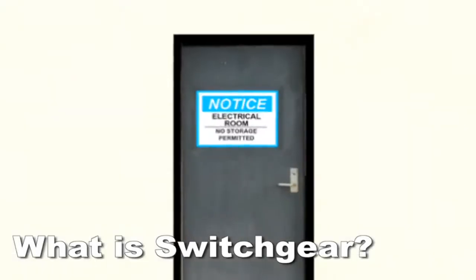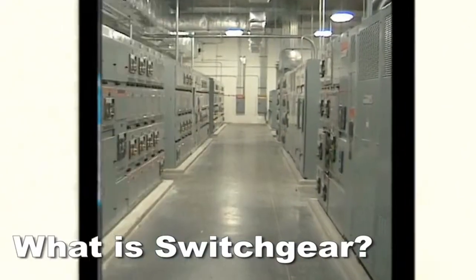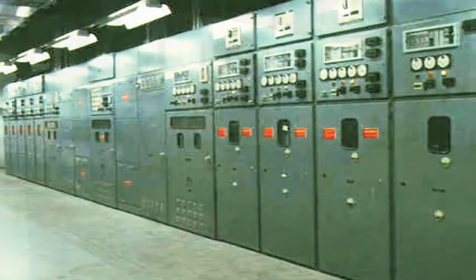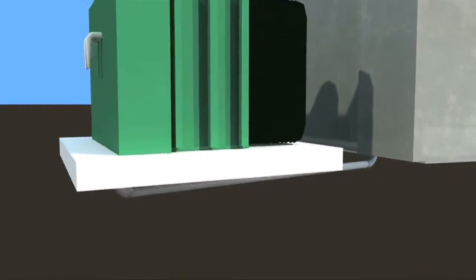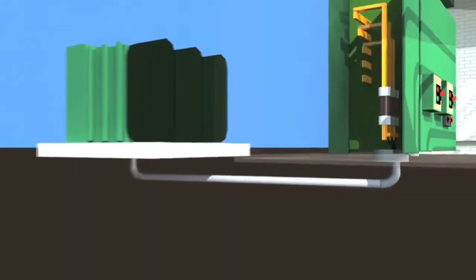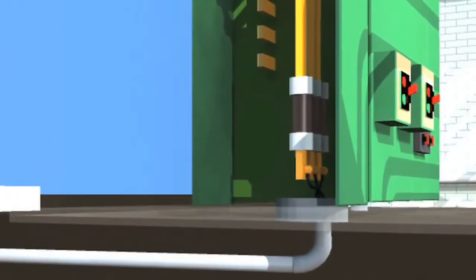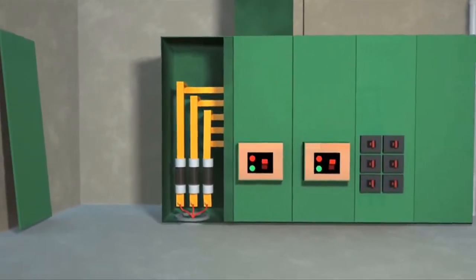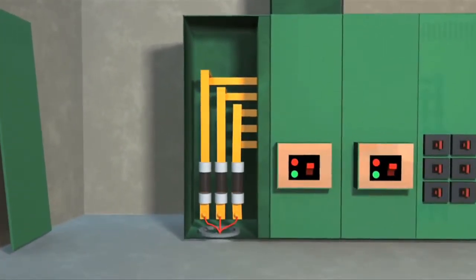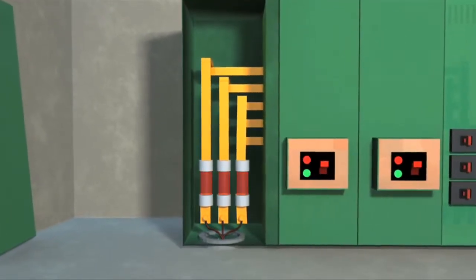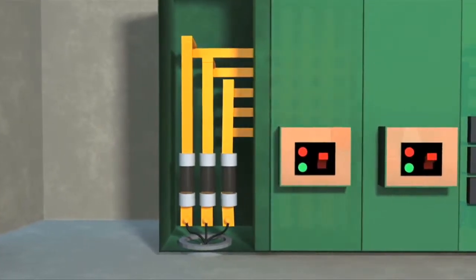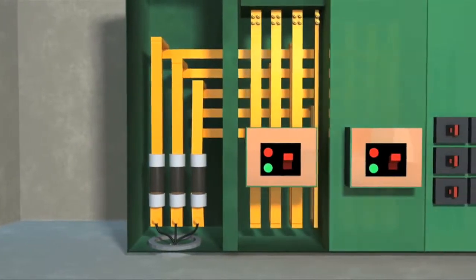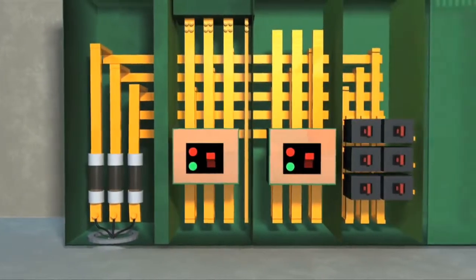What is switchgear? It's the beginning of the electrical distribution system inside the facility located in an electrical room. It is made up of several sections containing switches and or breakers. The first section receives the incoming power from the oil transformer. The wires are connected to a main breaker or in this example, they are attached to fuses. The fuses are connected to bus bar. Bus bar is either made up of copper or aluminum. The voltage travels through the bus bar to each section of connected switchgear, energizing each section.